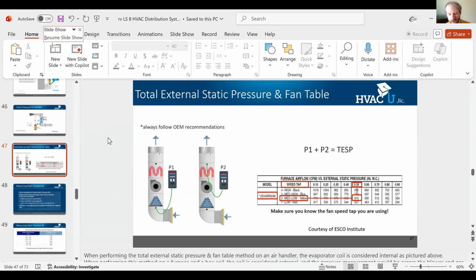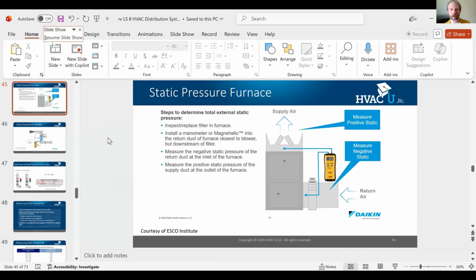And speaking of static pressure, it was interesting because I saw you testing after the filter. One of the things we look at with static pressure, and this is an extra LEED credit especially in version 4.1, and just a general best practice, is that if we want to be healthier in our homes, we want higher MERV systems. If you're testing after the filter and trying to determine if someone used a thicker or thinner filter with a higher rating, that's a drag on the system. I just had a project come back, and they tested and broke out in the visuals, very nice, where each static pressure number was coming from: 1 plus 2 plus 3. And it showed me the filter was responsible for this, and they told me that.